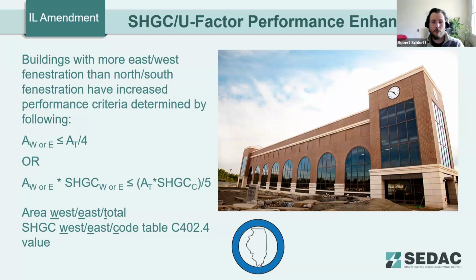The overall result of these requirements is that if the area of the east and west fenestration exceeds 25% of the total building fenestration area, then the east-west fenestration must have a 20% better performing solar heat gain coefficient than the base code minimum value. So again, this is aimed at trying to counteract high heat gains from east and west glazing. And this impacts rectangular buildings as well as square buildings. So just keep this in mind when you are designing from scratch, that significant amounts of east and west glazing do need to be addressed via this amendment.